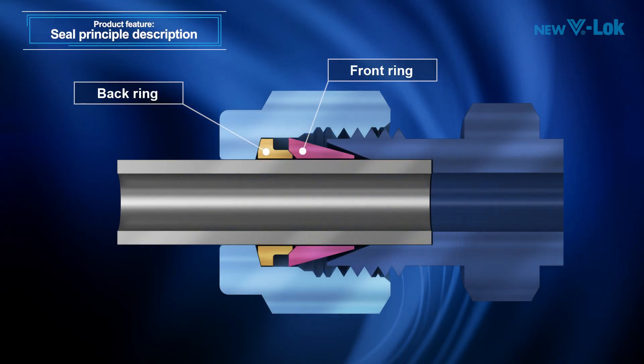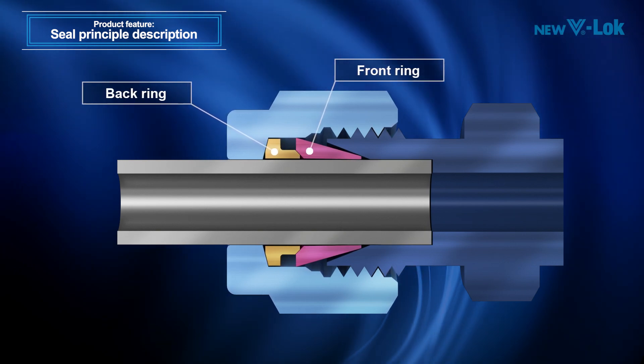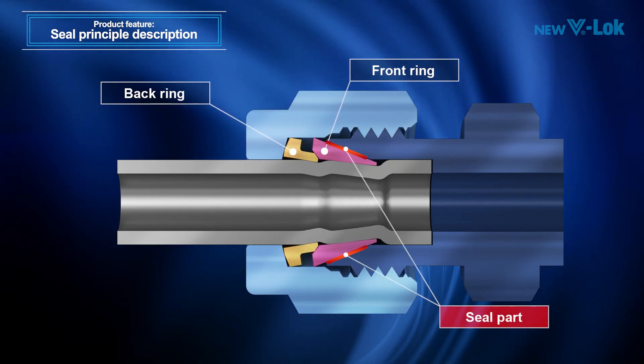We will now explain the seal principle of the V-Lok fitting. Turning the nut clockwise to tighten the fitting allows the back ring and the front ring to compress a tube for firm gripping, thus realizing a mechanism of preventing external leaks of fluid.